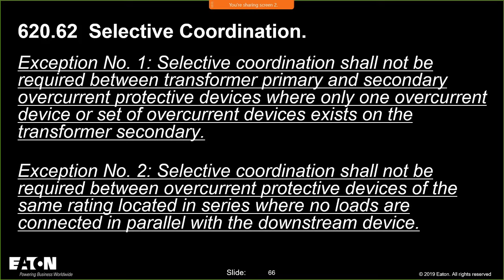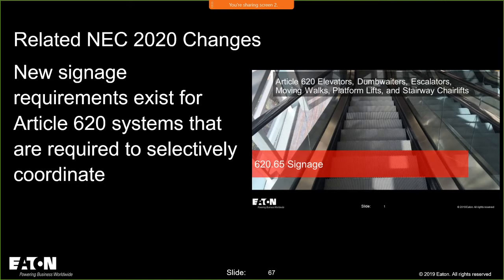Hopefully that makes sense. And then it shall not be required between overcurrent devices of the same rating in series with each other. So if I have two 100 amp breakers or two 100 amp fuses in series with each other, they take out the same load, so I don't have to worry about coordinating those two. Now, what happened in the 2020 cycle? Yeah, Dan, I agree. There probably should have been an exemption in the performance language like we did in 700 and 701. So, an opportunity for next cycle.